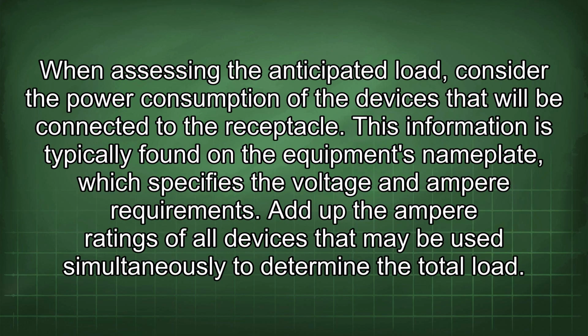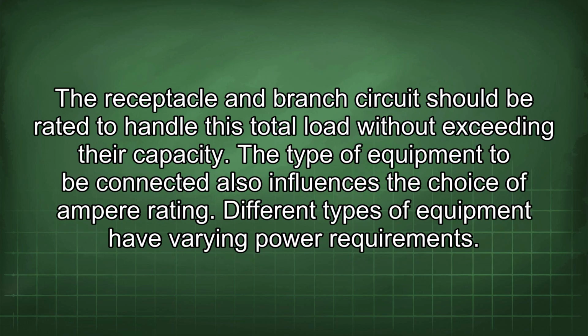overloads. When assessing the anticipated load, consider the power consumption of the devices that will be connected to the receptacle. This information is typically found on the equipment's nameplate, which specifies the voltage and ampere requirements. Add up the ampere ratings of all devices that may be used simultaneously to determine the total load. The receptacle and branch circuit should be rated to handle this total load without exceeding their capacity.